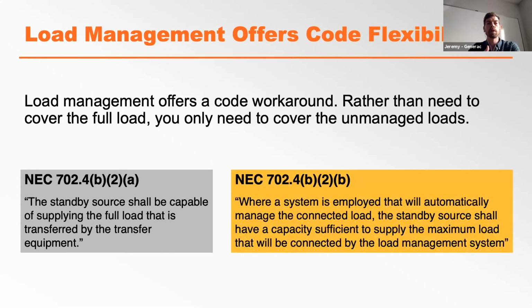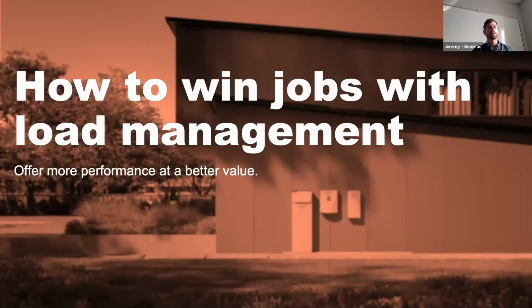Well, if you have been unfamiliar with load management up to this point, you may have also been unfamiliar with this other part of the code, part B, which basically says that if a load management system is in use, then the battery only needs to be sized for the maximum transferred load, the maximum load that will be connected by the load management system. And because a load management system prevents local load from exceeding the battery's capacity or capability, basically all you have to do is size your unmanaged essential loads to be at or under your battery's power, and then manage the rest. It's that easy. You can keep everything else, all the loads, in one panel, and still meet code when you employ load management. So that's a bit about what load management is, how it works, and why it's important.